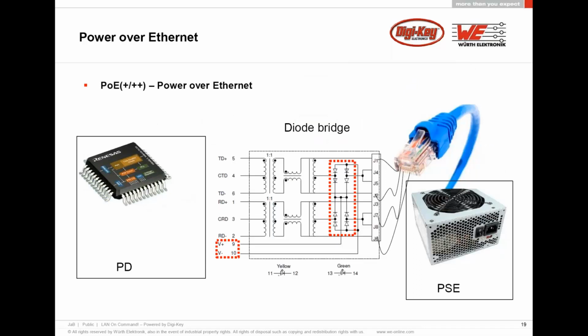What I want to show you here is the difference between an RJ45 for a PD and for a PSE. In this case, we have a diode bridge, and the diode bridge takes care that however I connect my PSE, I am for sure having the plus and minus on pin 9 and pin 10. Generally speaking, the PSE will be from one manufacturer and the PD from another manufacturer. So if we don't have the diode bridge, it can happen that with two different manufacturers for PSE and PD, I burn down my PD because the PSE might be giving me the plus on pin 10 and the minus on pin 9.